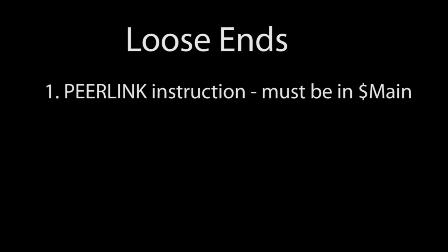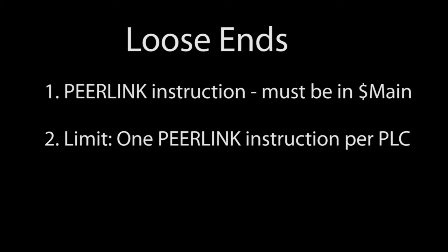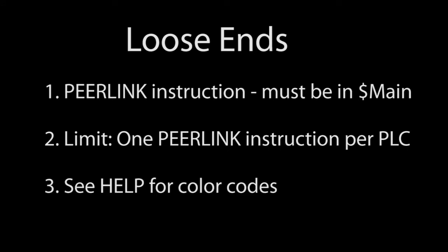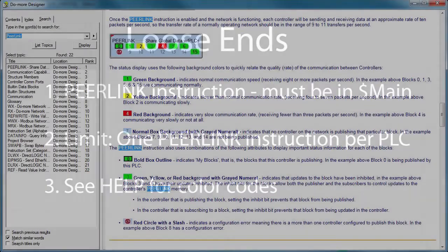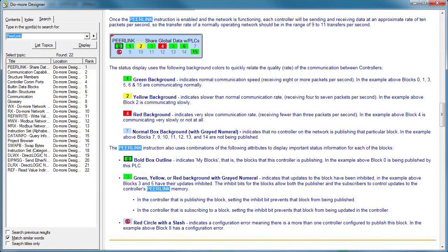A couple things to keep in mind. The PeerLink instruction has to be in the main program loop. You can only have one PeerLink instruction per PLC. And we saw how when two PLCs try to write to the same memory location, the status turned red. There's a whole bunch of different color status codes in the help file which at a glance tells you exactly what the PeerLink network is doing.